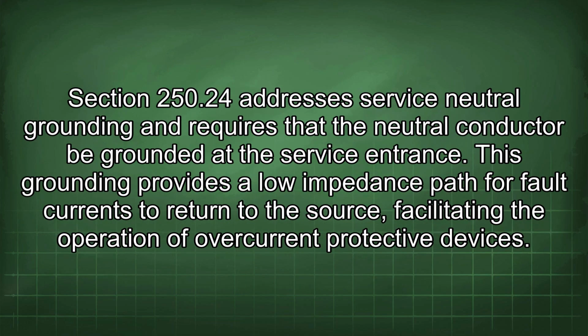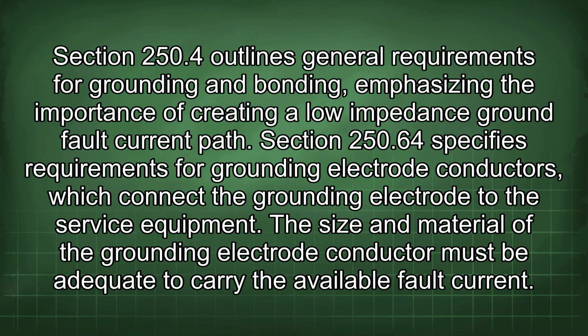Section 250.24 addresses service-neutral grounding and requires that the neutral conductor be grounded at the service entrance. This grounding provides a low-impedance path for fault currents to return to the source, facilitating the operation of overcurrent protective devices.